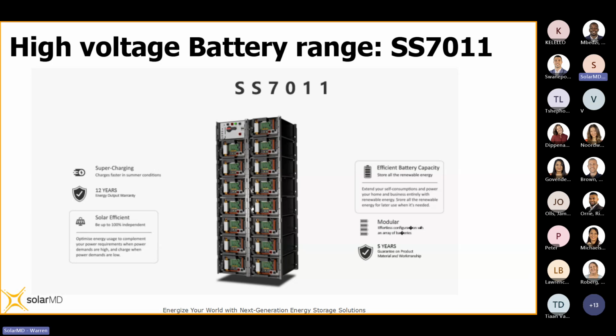In my opinion, and this is open to discussion, especially with the experts at IBC, that sort of threshold is normally about 50 kilowatts, I would say. So if a customer is needing a storage solution or solar solution and you're looking at a 50 kilowatt inverter, or trying to meet that sort of demand, that's the point at which you should consider looking at a high voltage solution. But that's just my opinion.